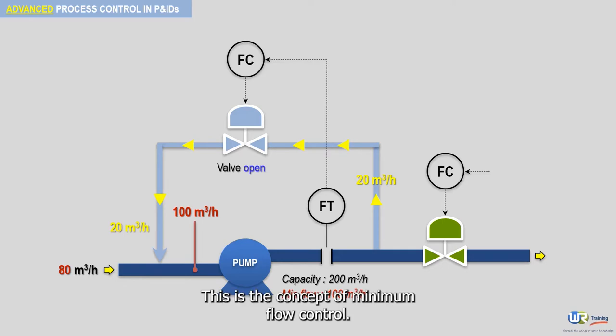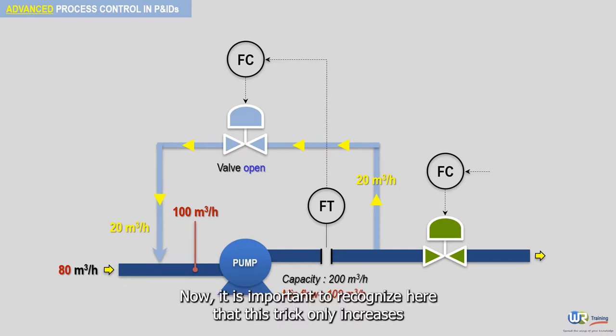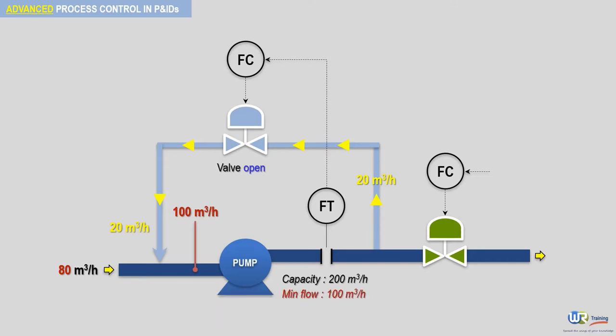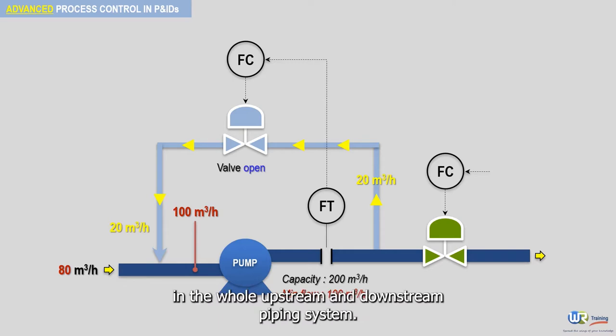This is the concept of minimum flow control. Now it is important to recognize that this trick only increases the flow rate inside the recirculation loop to a number higher than 100 cubic meters per hour to fool the pump. We are not able to increase the overall flow in the whole upstream and downstream piping system.